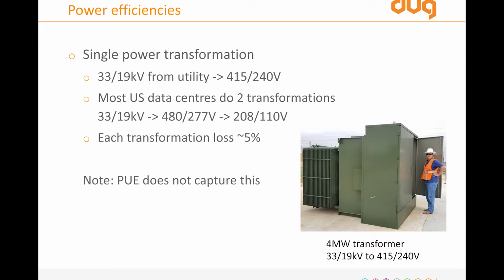So again, single transformation gives us two things. It saves us about 5% on losses because most US data centers have to run two transformations. They have 33,000 volts coming in somewhere, and then they take 480 volts from the utility, and you can't use that in a computer because 480 volts is 277 volts single phase. The power supply on the back won't take it. So you then have to down transform again. So by taking 33,000 volts, you actually get on a better power tariff because the energy utility charges you for that first transformation. And there's a loss, 5%, 3%, 2% in that process. By doing a single transformation, we cut down to just one loss through that transformation instead of 2 or 3.